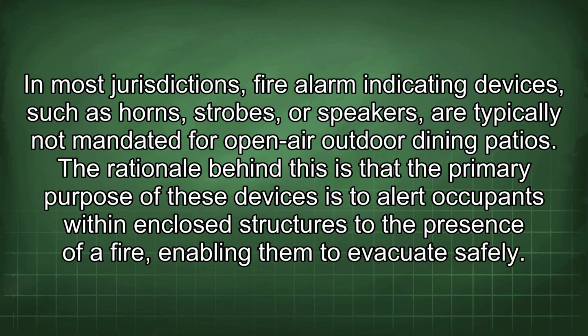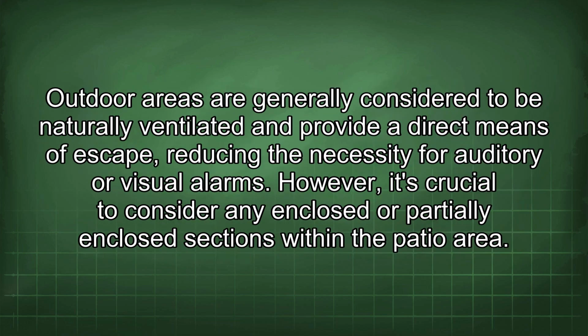In most jurisdictions, fire alarm indicating devices such as horns, strobes, or speakers are typically not mandated for open-air outdoor dining patios. The rationale behind this is that the primary purpose of these devices is to alert occupants within enclosed structures to the presence of a fire, enabling them to evacuate safely. Outdoor areas are generally considered to be naturally ventilated and provide a direct means of escape, reducing the necessity for auditory or visual alarms. However, it's crucial to consider any enclosed or partially enclosed sections within a patio area.